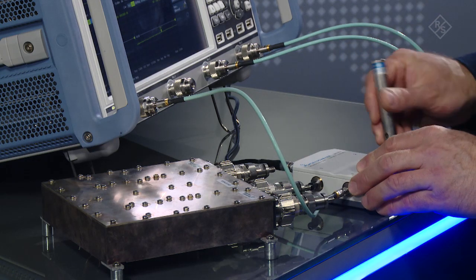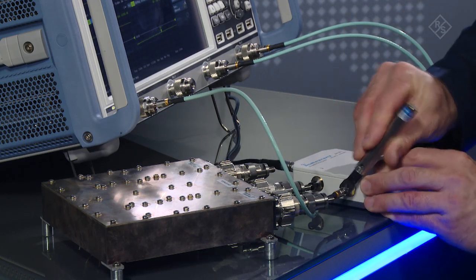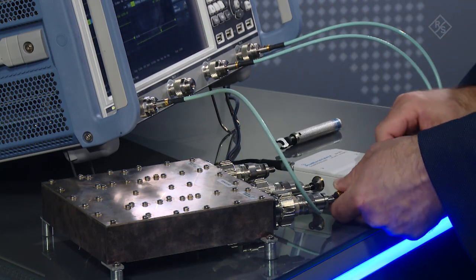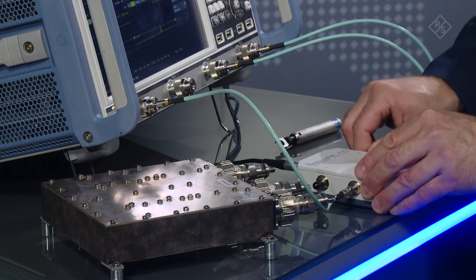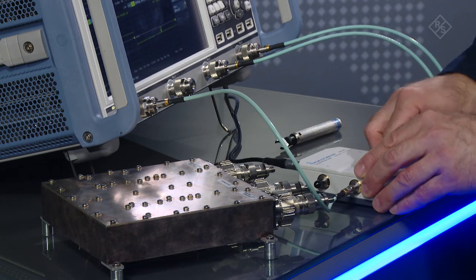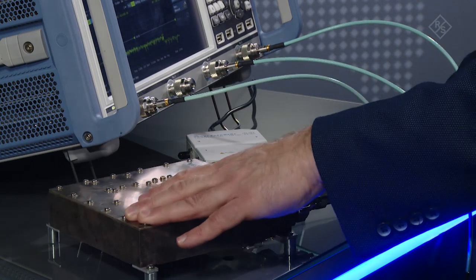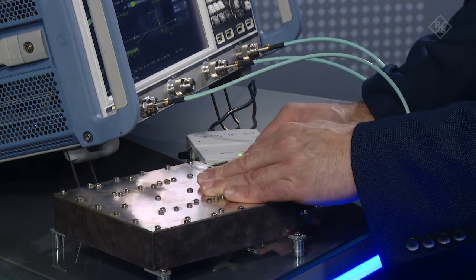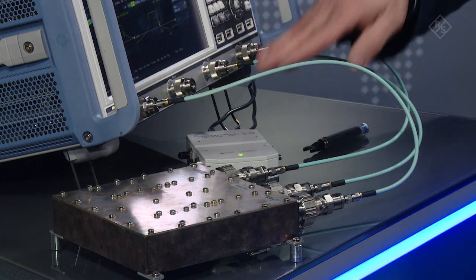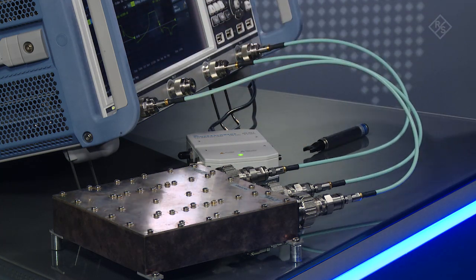We'll reconnect the duplexer. For optimum results, use proper connector care — there's a fantastic presentation from Rohde & Schwarz on this — and never rotate the cable itself. After properly connecting the duplexer, making sure we connect the correct band to the correct test ports — in this case low band to port 1, antenna to port 2, and high band to port 4 — we have the measurement results.